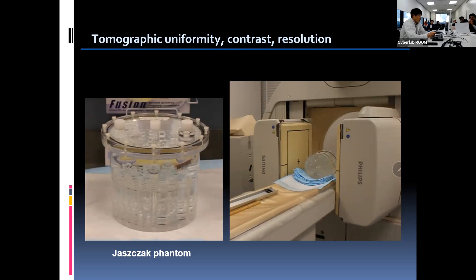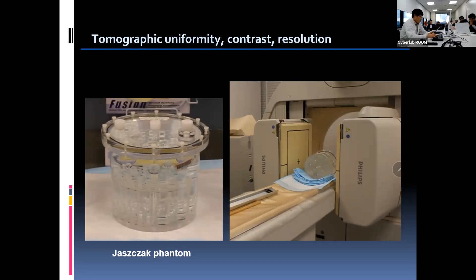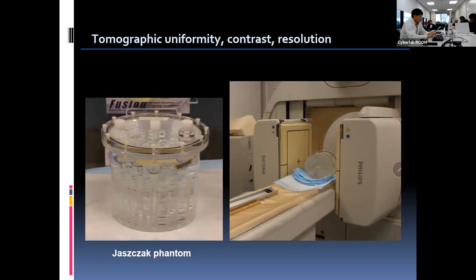For this test, we use a Jaszczak SPECT phantom, which is fillable with a solution containing radioactive material. 15–20 millicuries of technetium need to be thoroughly mixed with water inside the phantom for uniform distribution of activity. Then the phantom is placed between the detectors, centered on the field of view for SPECT acquisition. It is important that the phantom be positioned parallel to the scanning table to get proper imaging for evaluation. The SPECT acquisition is performed in 180-degree dual head position or 360-degree total angle of rotation, acquiring 25 to 30 million counts total.